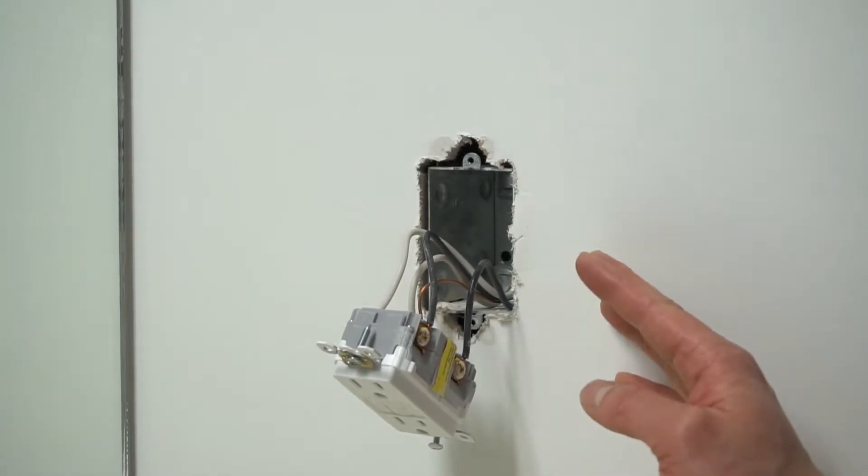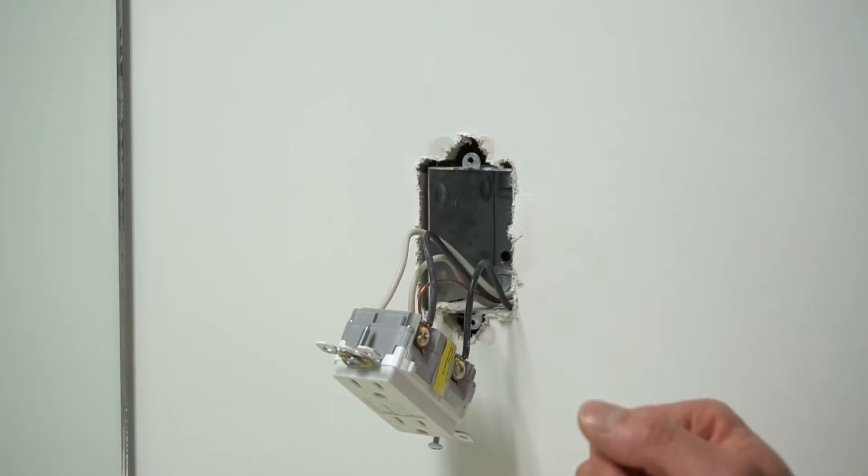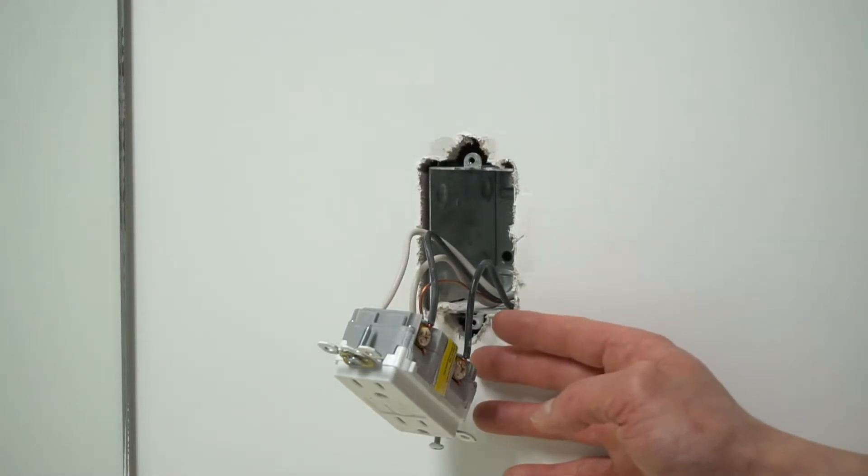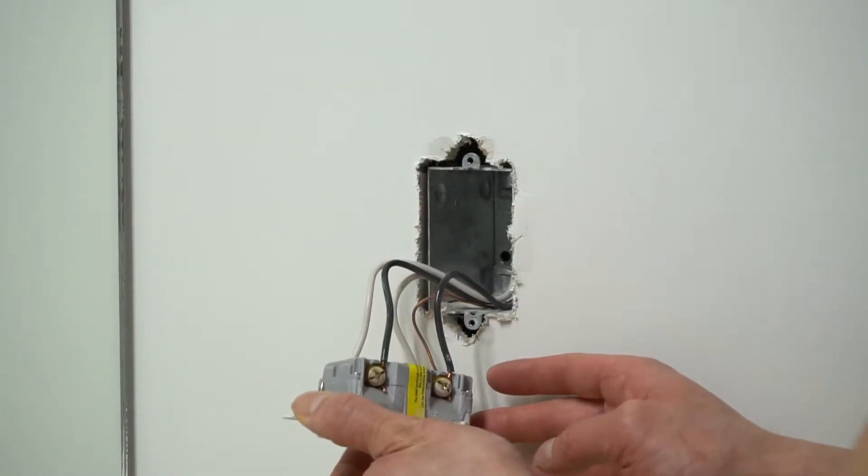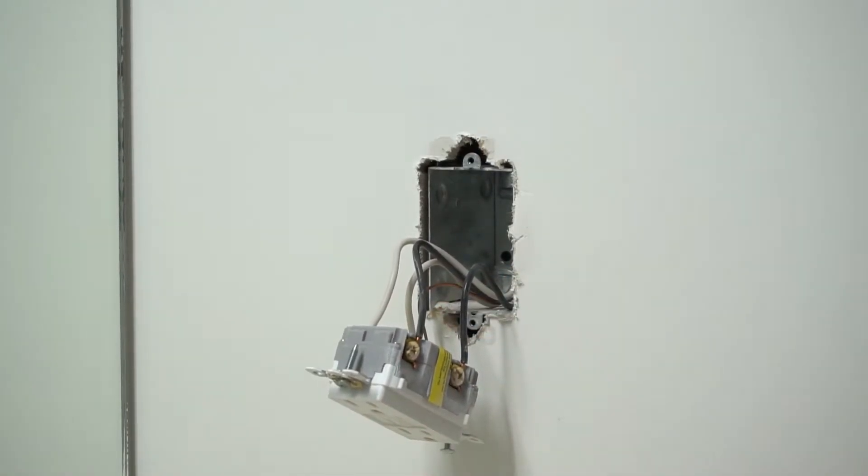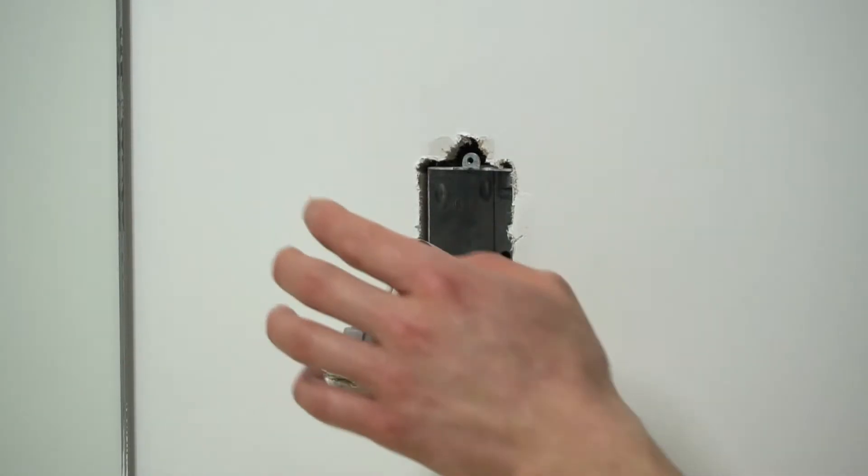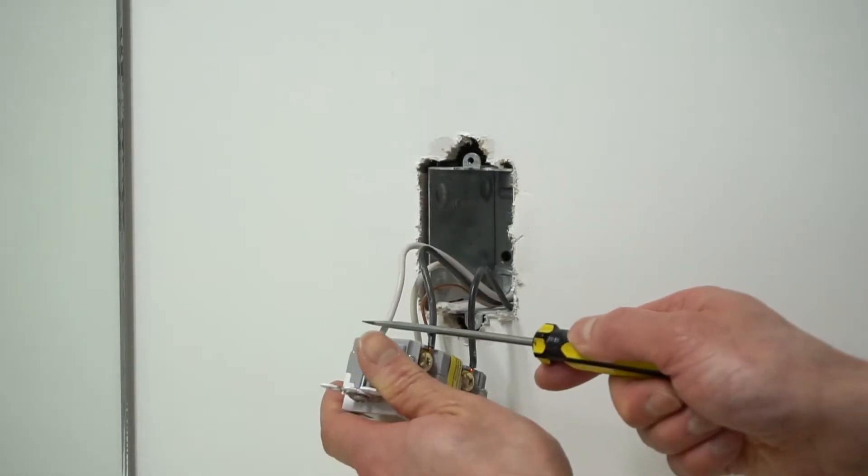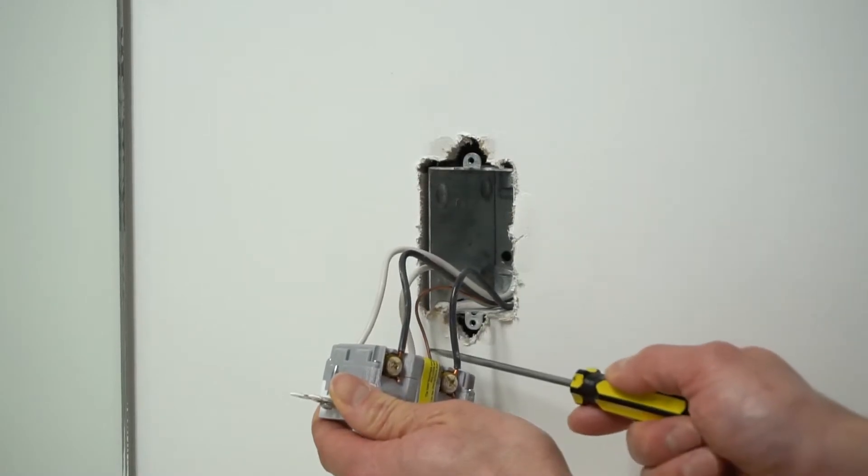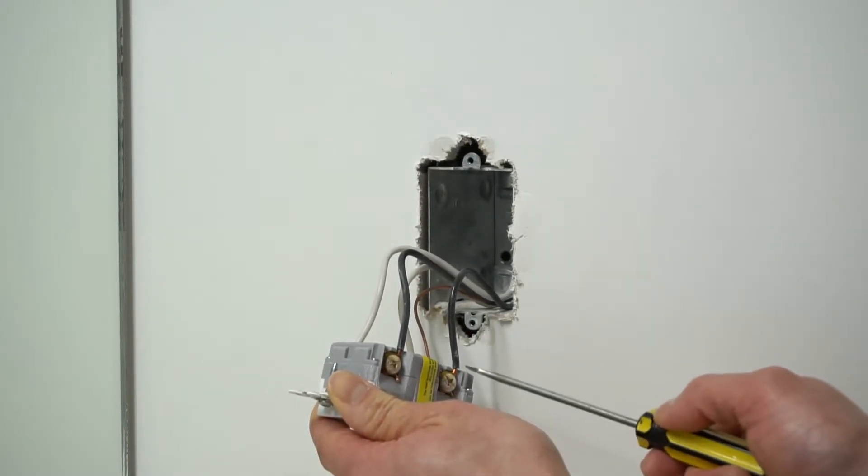That's only if your breaker panel is labeled correctly and that you have switched off the correct breaker. Now it's very important when you take off these wires from the plug, do not mix and match. Remember that one set is the load side and the other side is the line side, the feed from the panel.